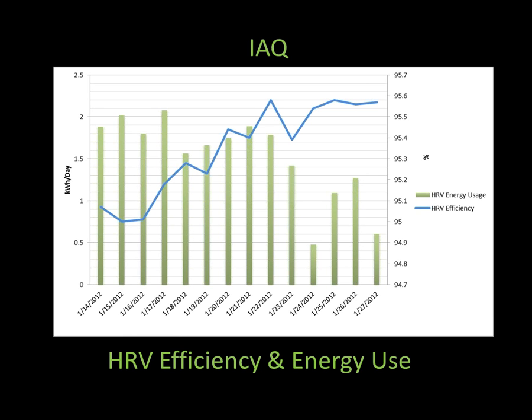And here we are looking at the indoor air quality and the efficiency of the unit, which we've also been tracking, and that seems to be matching the manufacturer's specifications. So we're looking on average at about 95% efficiency, which means that the air coming out of the supply duct is very close to the air that was being exhausted. And that is important from a comfort standpoint, so you aren't dumping 50-degree air into rooms throughout the house.